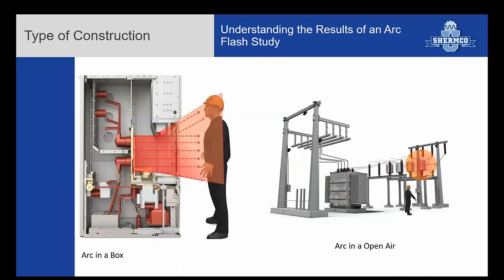And then when we're talking about construction, there's arc in a box versus arc in open air. Arc in a box, basically all of the energy is projected at the worker, where arc in open air, shown on the right, the arc can go in all directions and only a portion of the energy will be directed towards the worker. So it's another term used, and it depends on the type of construction being used at your site.